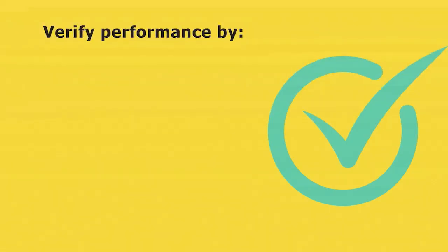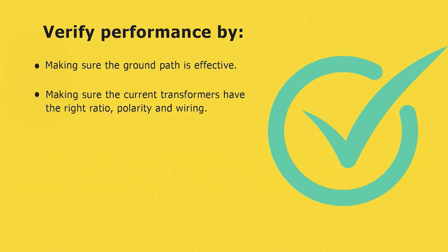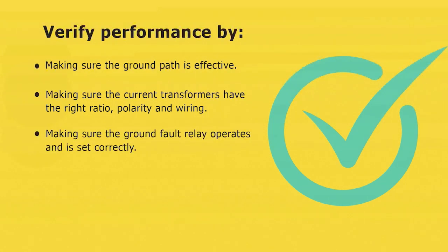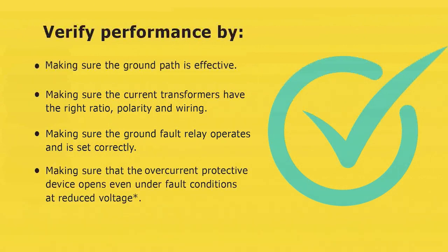So when we verify performance, we're going to make sure the ground path is effective, the design is right, and it's been installed properly. The CTs, the current transformers, have the right ratio, polarity, and wiring. The ground fault relay operates and is set correctly. And then we're going to make sure that the overcurrent protective device opens even under fault conditions at reduced voltage. That reduced voltage is 55% of control power voltage on AC or 80% of control power voltage on DC.